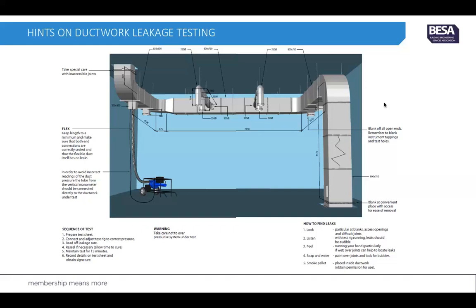To find the leaks: first, physically look to make sure there are no blanks or access doors missing from the system. Sometimes you can hear air running out of a joint, or actually feel it with your hand. If it's still very difficult to find — perhaps on a high-pressure system — you may need to use soap and water to create bubbles showing where the air is leaking. On some occasions a smoke pellet can be used, but you must ensure this is cleared with the client beforehand in case any fire alarms or smoke detectors are triggered.